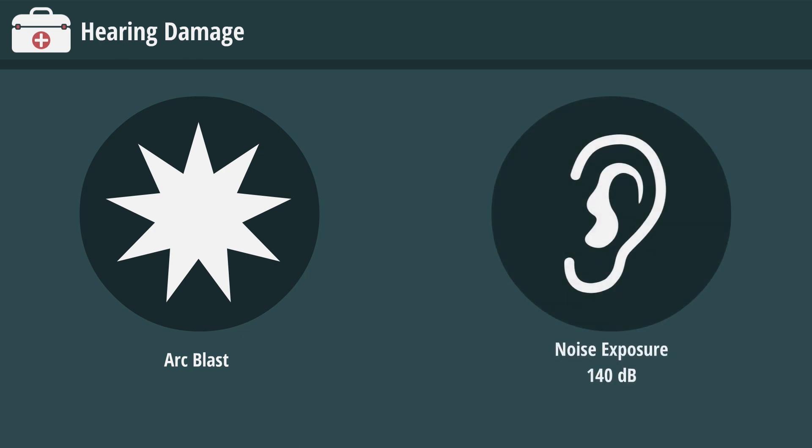The sudden expansion of an arc blast is very loud and can create a noise exposure up to 140 decibels at a distance of 2 feet, which can cause permanent hearing damage.